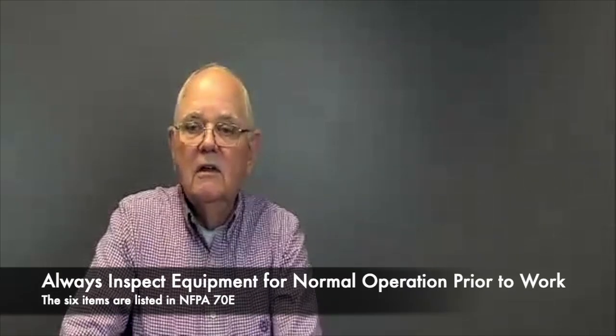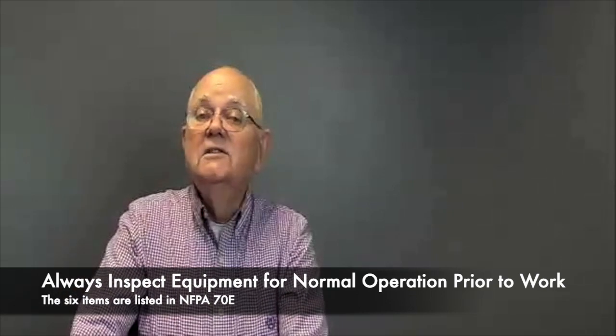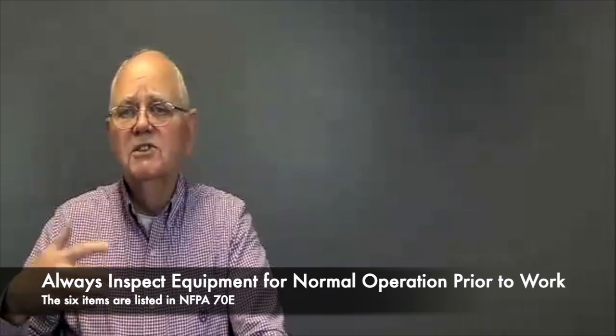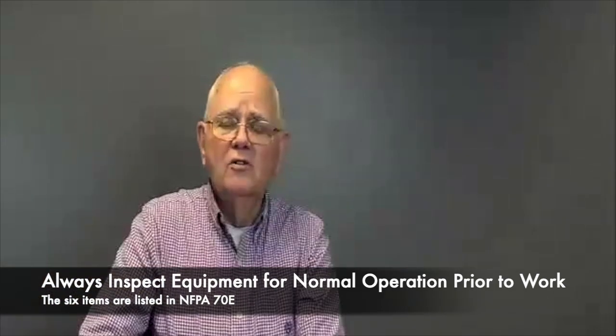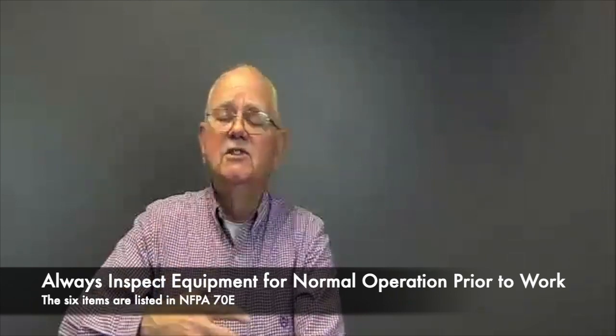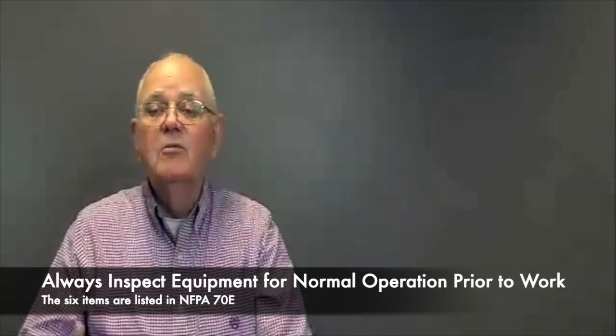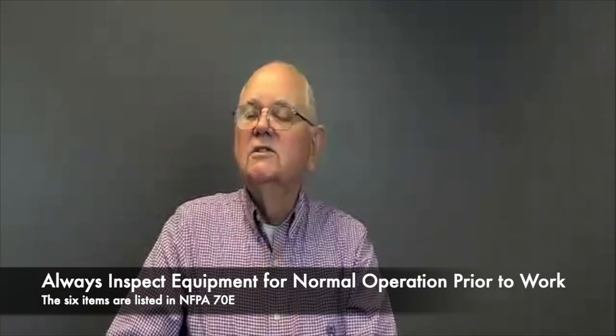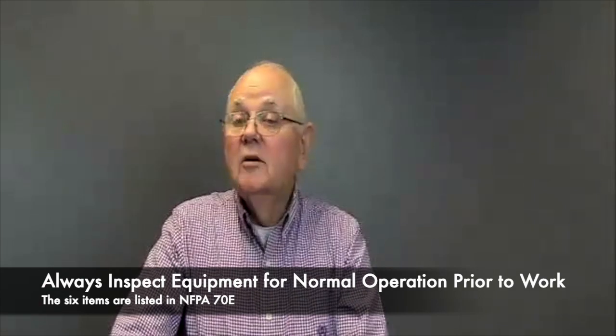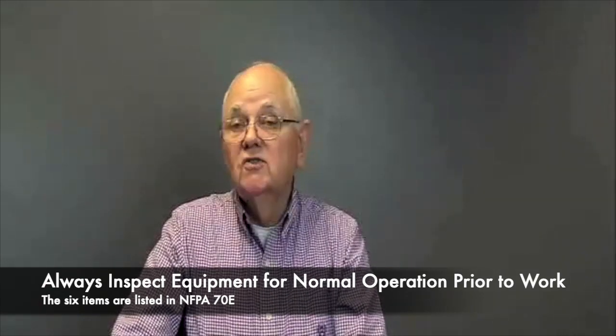I have to make sure that my equipment is suitable for normal operation. And so that's those 6 points that are in 70E, where it talks about the equipment's been properly installed and maintained, the doors are closed and secured, and all the covers are in place, and it's used in accordance with the manufacturer's listing and labeling and all of those requirements, as well as there's no signs of impending failure. And that comes with experience and knowledge and training, learn how to inspect that equipment for normal operation. So that's a whole separate issue but you definitely need to be cognizant of that anytime you're going to work on medium voltage. So that in a nutshell is medium voltage safety then.